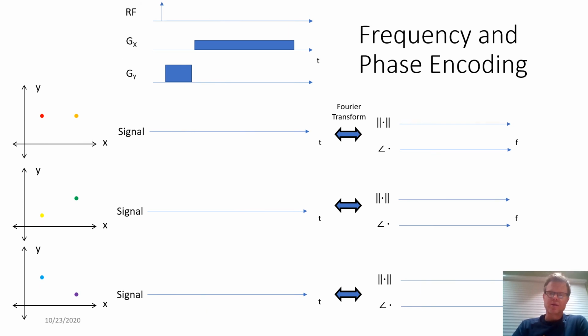And if we go to an example here of an even larger phase encoding gradient, now we might get something like even more phase accumulation for these higher y offsets, followed by low frequency, low location in x. So again, we're still at the frequency encoding, so the position of these peaks in frequency doesn't change, but actually we may be back here to where we've gone.